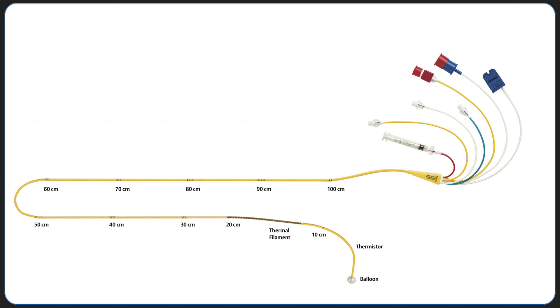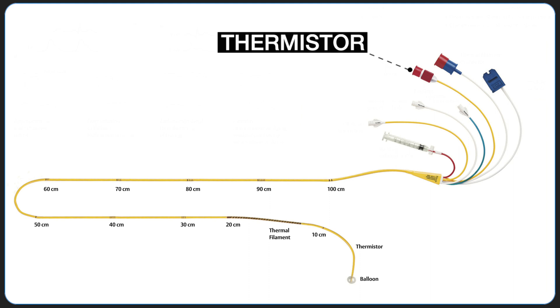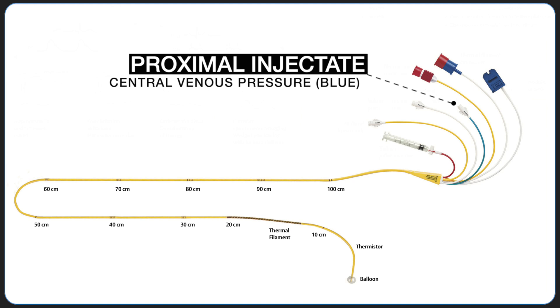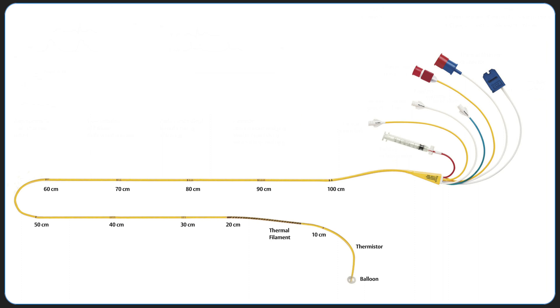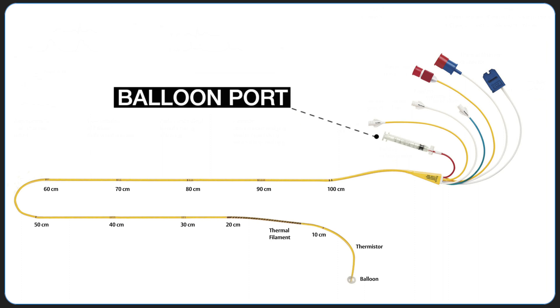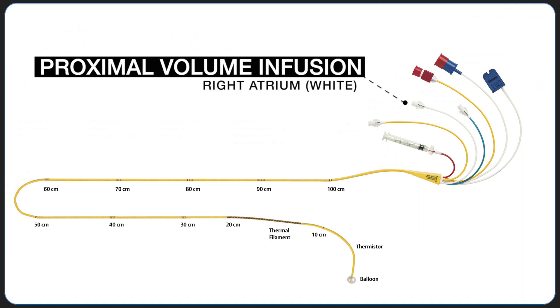For a standard VIP catheter, the lumens include the thermistor port, which measures blood temperature for cardiac output calculations; the blue CVP, or proximal injectate port, which terminates 30 cm from the catheter tip; the yellow, or PA distal tip port, which terminates at the tip of the catheter; the balloon port, which is used to inflate the balloon at the tip of the catheter; and the white right atrial, or proximal volume infusion port, which terminates 31 cm from the catheter tip.